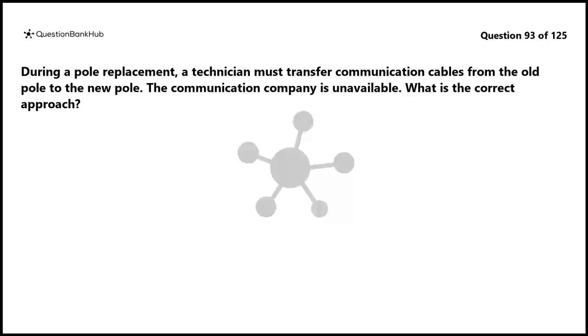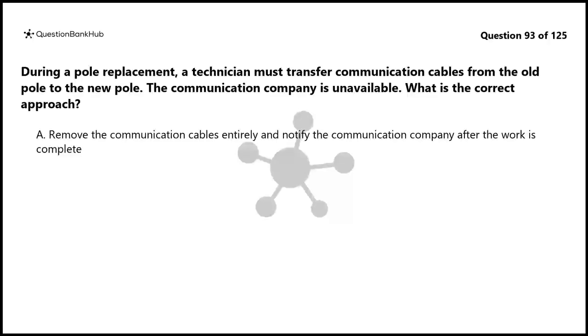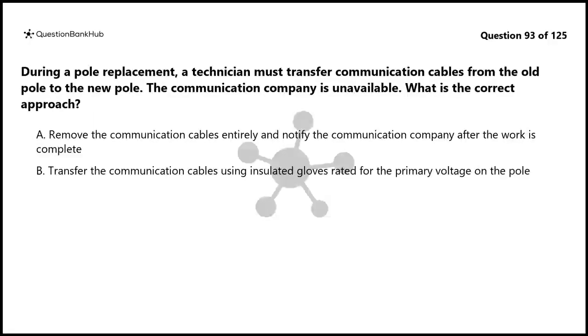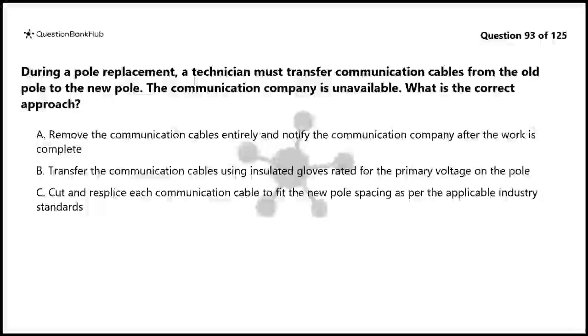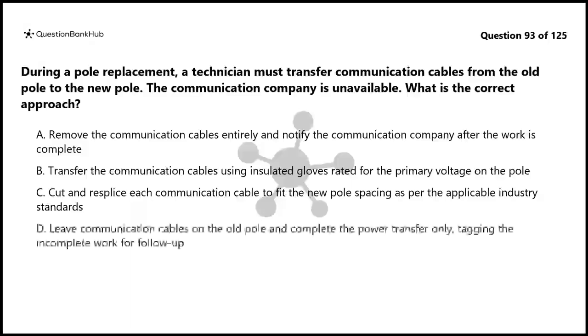Question 93. During a pole replacement, a technician must transfer communication cables from the old pole to the new pole. The communication company is unavailable. What is the correct approach? A. Remove the communication cables entirely and notify the communication company after the work is complete. B. Transfer the communication cables using insulated gloves rated for the primary voltage on the pole. C. Cut and resplice each communication cable to fit the new pole spacing as per the applicable industry standards. D. Leave communication cables on the old pole and complete the power transfer only, tagging the incomplete work for follow-up.